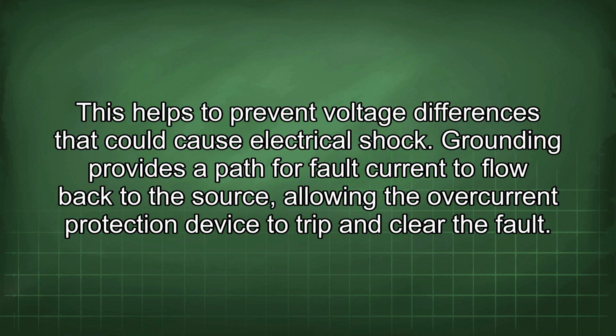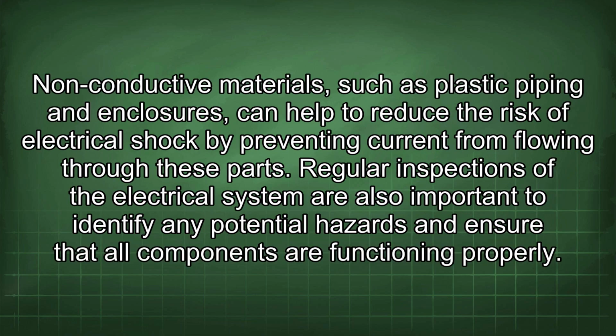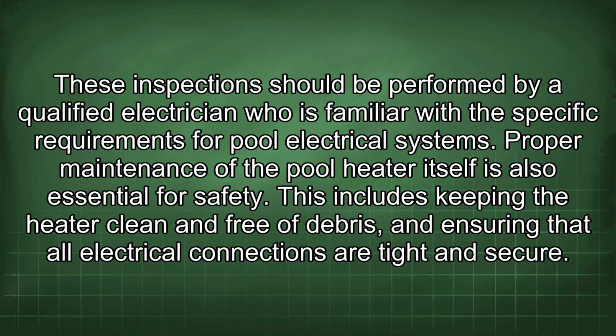Grounding provides a path for fault current to flow back to the source, allowing the overcurrent protection device to trip and clear the fault. Non-conductive materials, such as plastic piping and enclosures, can help to reduce the risk of electrical shock by preventing current from flowing through these parts. Regular inspections of the electrical system are also important to identify any potential hazards and ensure that all components are functioning properly.